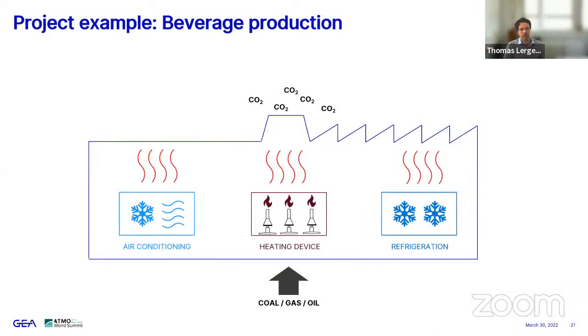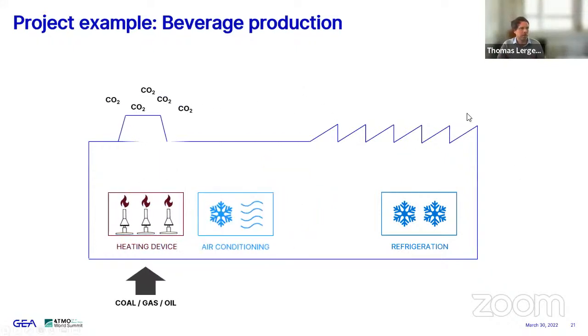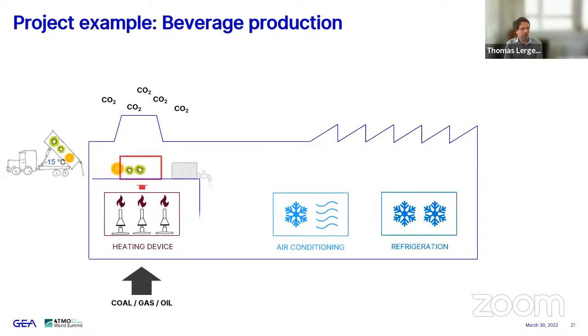And a typical, this is, again, you've seen this in the beginning, the typical classic layout of old factories, not only old factories, still existing factories with air conditioning, refrigeration devices, and the classic boiler. This is an example from the beverage industry, but it's very typical. Yeah, food, beverage, dairy industries. In this case, we have a smoothie production, and there are fruits. They come in a little bit deep frozen at minus 15 degrees Celsius. So the first heating demand that such a factory has is to defrost the incoming products, and they have a kind of conveyor belt or whatsoever, and then they have a box where they heat it up to about plus 60 degrees Celsius, and then it's squeezed and pressed for the juice.